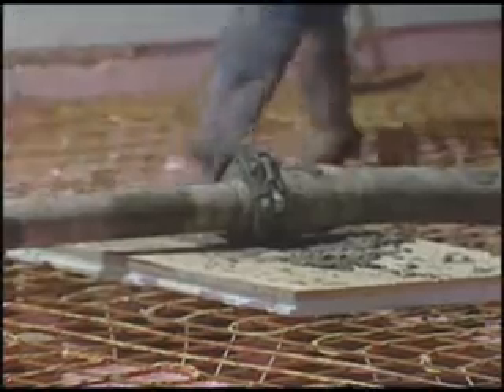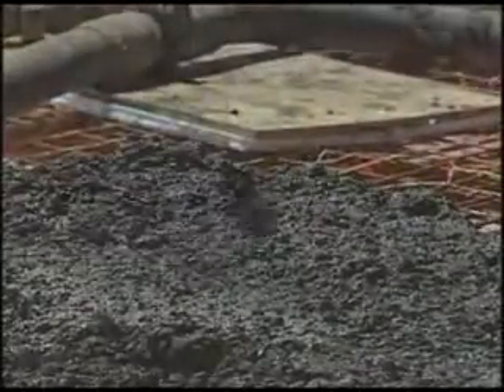When the pump is running and concrete is poured on the mesh, always keep the pipe raised so its nozzle will not touch the cables. Spread the cables with a straight-edge scraper, being careful not to snag them. Do not use a notched scraper. Also, be very careful of the cables when you move on the mesh. During the stage of concrete compaction, shake the mesh carefully so as not to damage the cables.